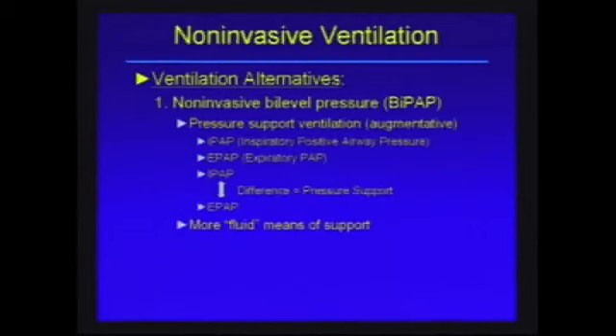And so if it's working correctly, it should just follow your breathing pattern. When you breathe in, it should move to the higher IPAP level to give you this extra airflow to help you take a bigger breath. Basically, it decreases your work of breathing. You don't have to breathe in as deeply because the machine does the work. But it doesn't control your breathing. It just allows you to take a bigger breath, so it augments your breathing.